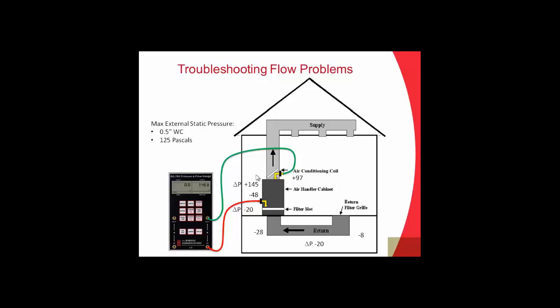And a lot of air handlers, typically you'll see 0.5 inches of water column, which is 125 pascals, or maybe 0.7 inches of water column. So that's the recommended total external static pressure for that given air handler. And if you go much higher than that, you're going to start affecting the life of that motor. You're going to shorten the life of that motor if you're running too high a static. So in this case, we've got 145 for a total, and it really should be 125 to be within the right range.